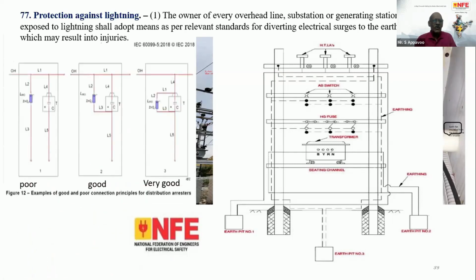So it is due to the wrong practice. How to do it? There is also a provision in the IEC. For example, if it is provided away, then it is a poor system. It is not interconnected. If it is interconnected, it's a good system. This is very good because of the loop. So ultimately, as the loop becomes closer and closer, it is interconnected. But unfortunately, we are not observing this. We are mostly following this type of configuration, which should be rectified.